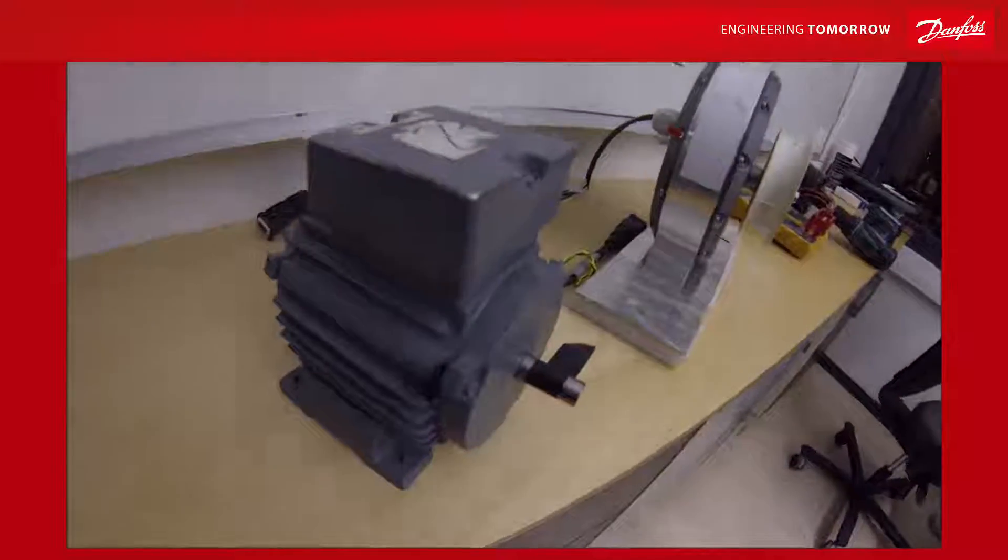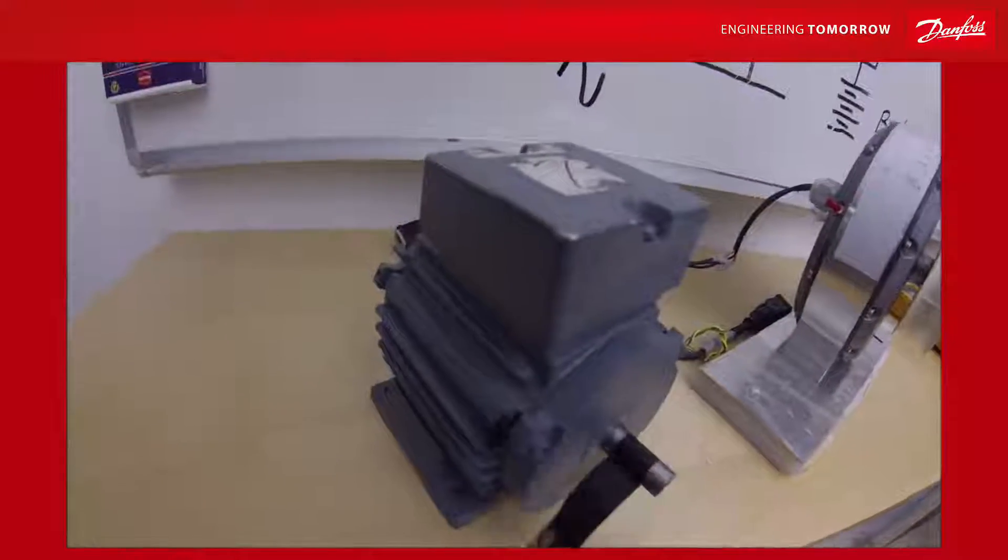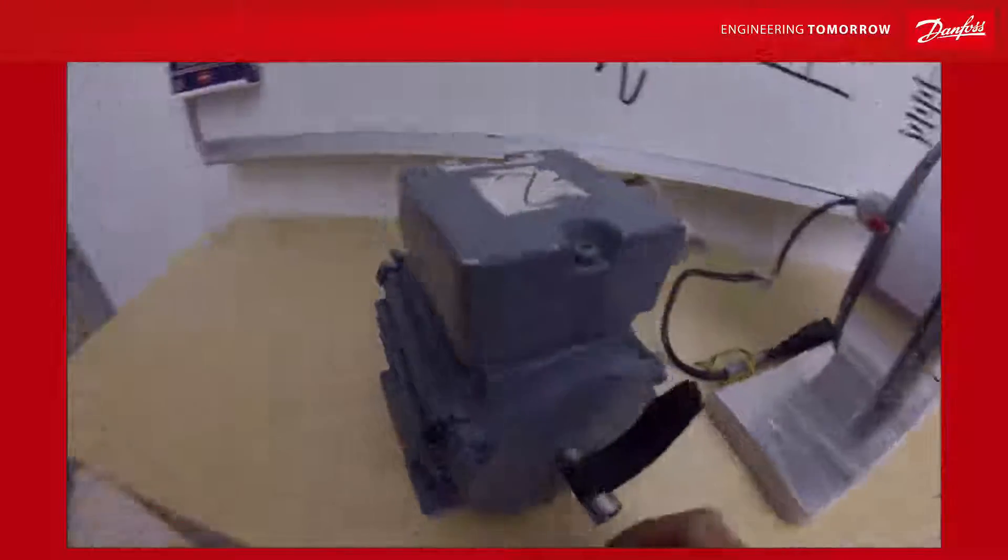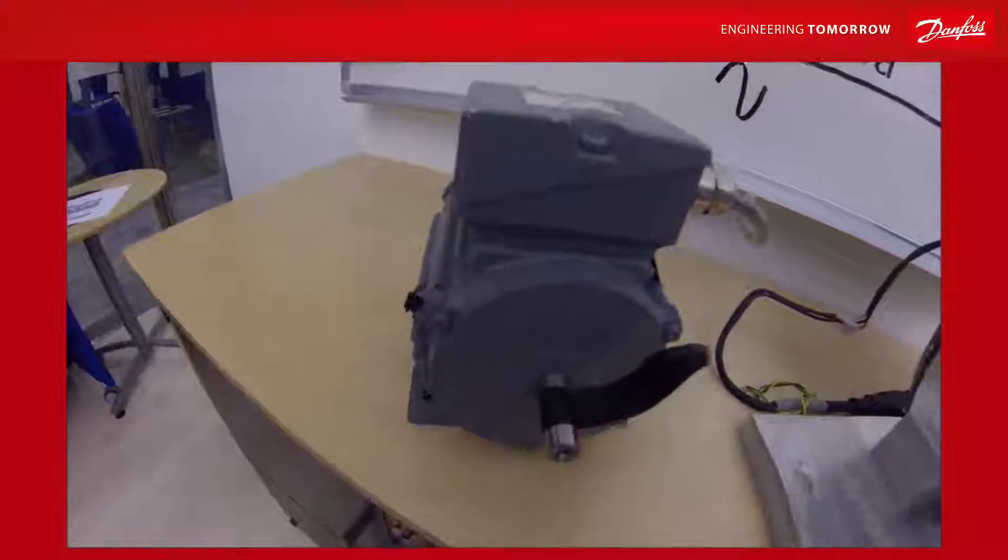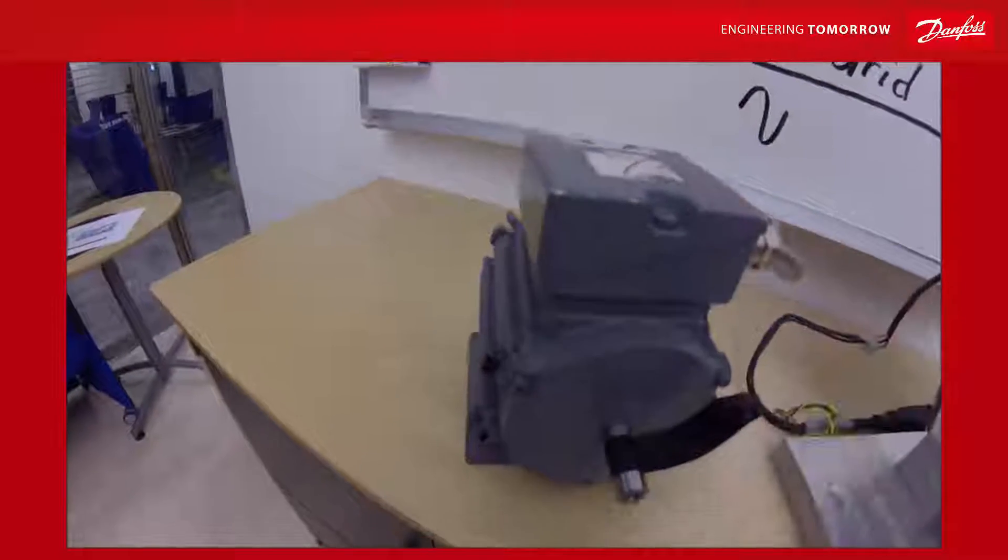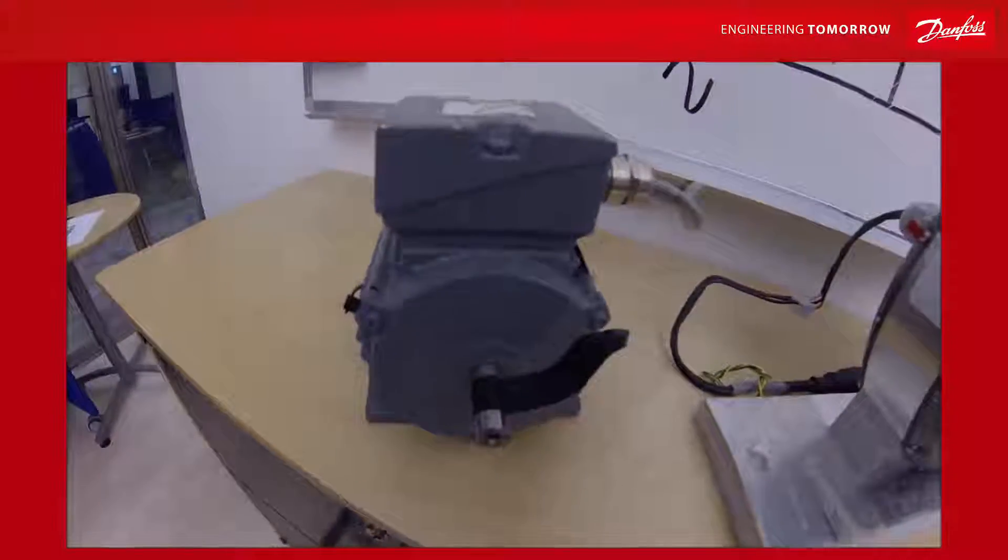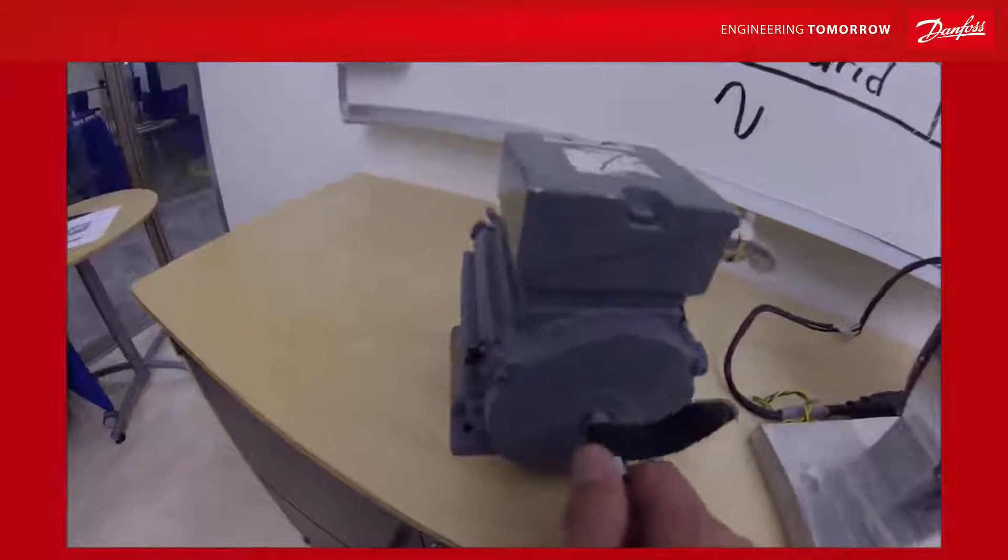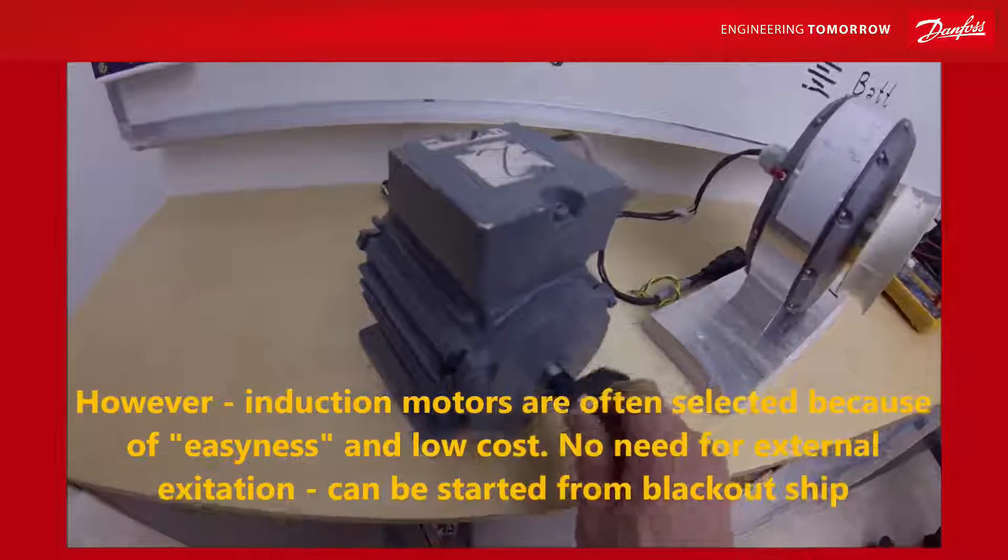Machines utilized for shaft generator could be asynchronous generator like this. Asynchronous motors and generators need to be magnetized from the outside continuously. The current running here, a reactive current of about 40% of the motor nominal, causes higher losses. So induction motors are not the highest efficiency for generator use.